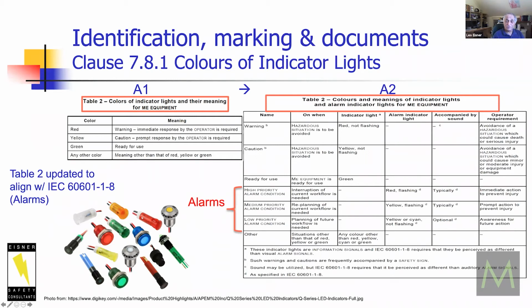So there's risk management sort of buried in here, with reference to 60601-1-8 in multiple places in the footnotes, tying you to the risk management aspect of 60601-1-8. As Luke also mentioned, risk management is embedded in 60601-1. This is a huge gap assessment that almost every medical electrical device is really going to have to go through, from A1, which was tiny and almost irrelevant as written, to what A2 is now.